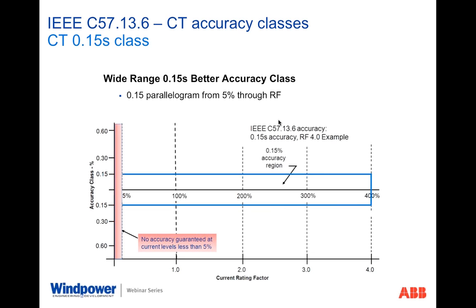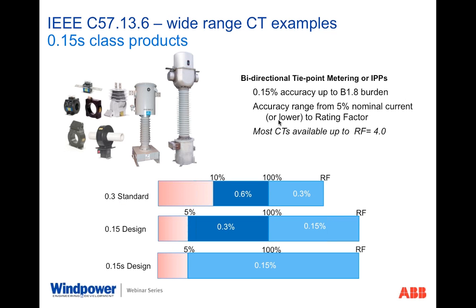Now, along came, of course, with our requirements, the need to provide products into the 0.15 class. And as you see here, we do have a lot of products out there, all the way from 600 volt, all the way up through 500 kV, even up to 765 kV, that will meet the 0.15 class performance over the wide range. So when you look at the illustration, you can sort of see where we've morphed relative to the accuracy classes available. The traditional 0.3 class has a big span of pink there. The 0.15 design tightened up on the pink region of unknown measurement accuracy, and also gave us better performance in the basic line from 5% all the way up to the rating factor value. Then the 0.15S design, again, 0.15 over the wide range. So that's what we call a wide range design. Some folks call them extended range. But in this case, 0.15 over the entire range, but the commitment stops at 5%. And that's a concern about wind farm development.